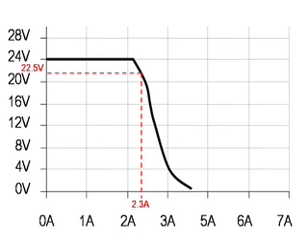For example, if the current increases to 2.3 amps, the output voltage will drop to approximately 22.5 volts DC, which for the typical load is still enough voltage to operate for a short period of time. So during an overload situation, constant power is maintained with no shutdown of the power supply.